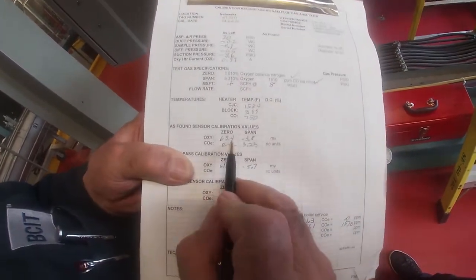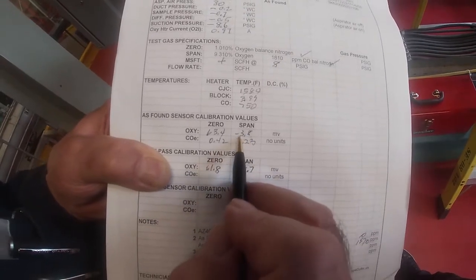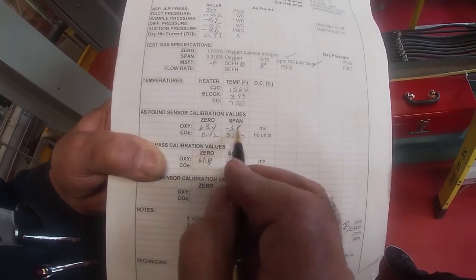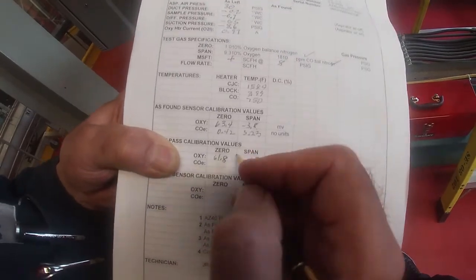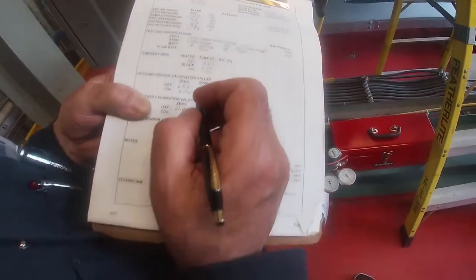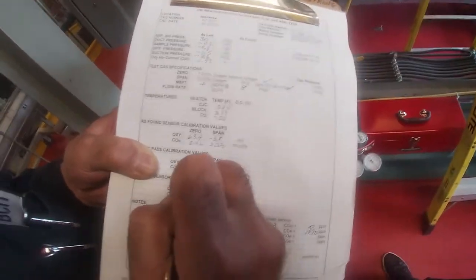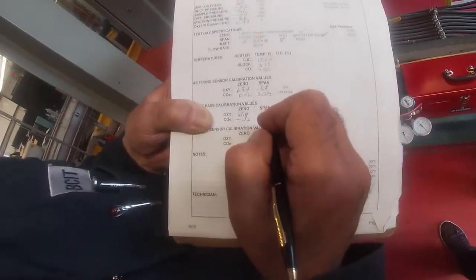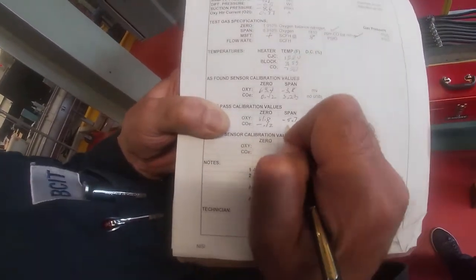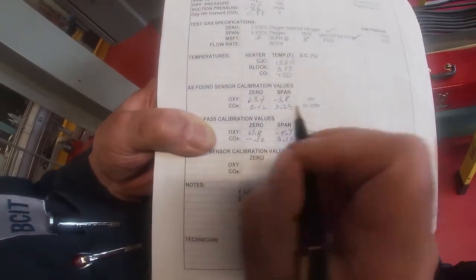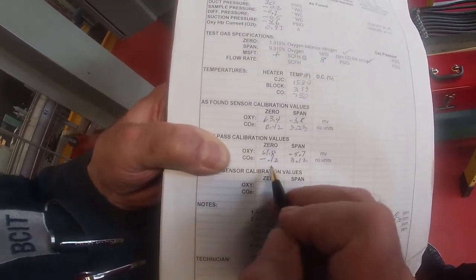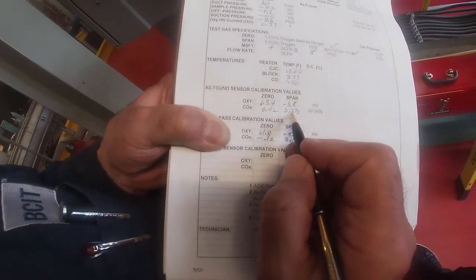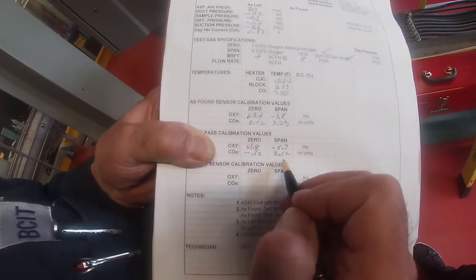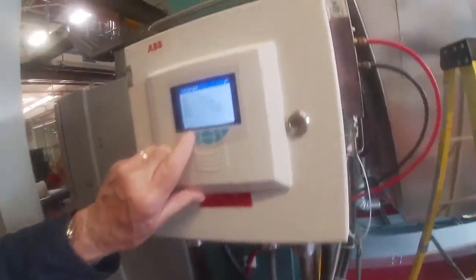Minus 5.7. So you can see it's changed a bit. It was 63.4, it's now 61.8 on the 0, and its span was minus 3.8, and it's now minus 5.7. On the CO, the 0 is minus 0.12, and the span for the CO is 3.12. And again, they moved a little bit, 0.42 to minus 0.12, and 3.23 up to 3.12. So they have moved. I'm going to exit.